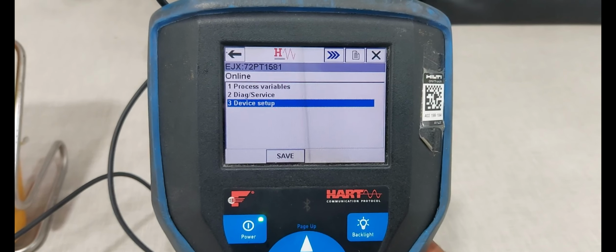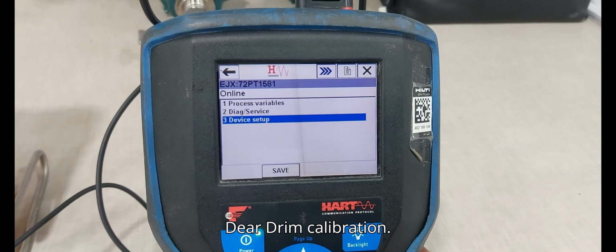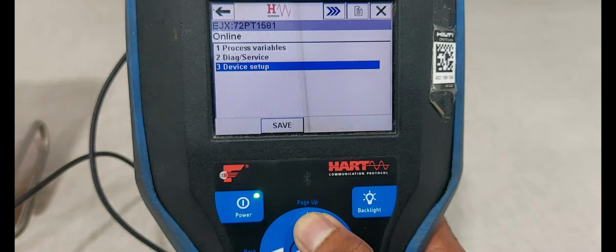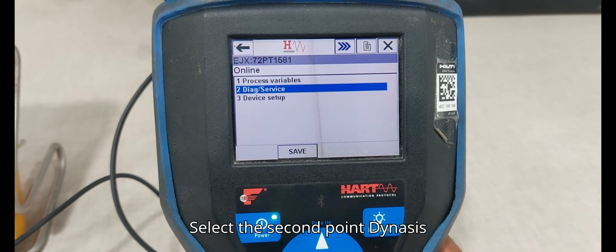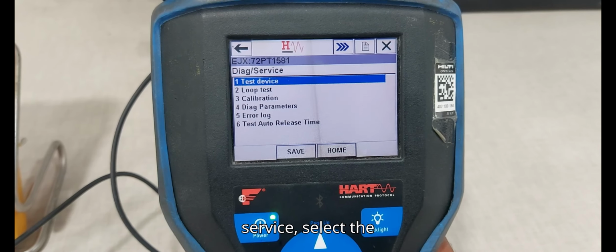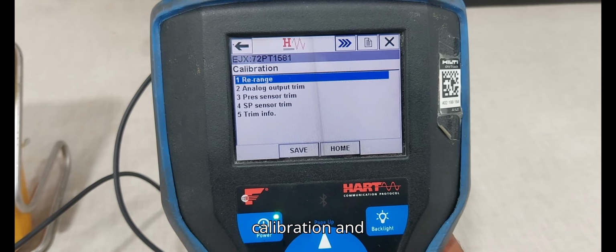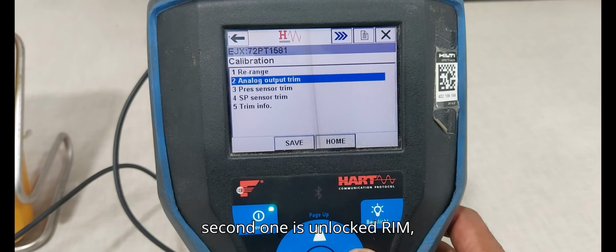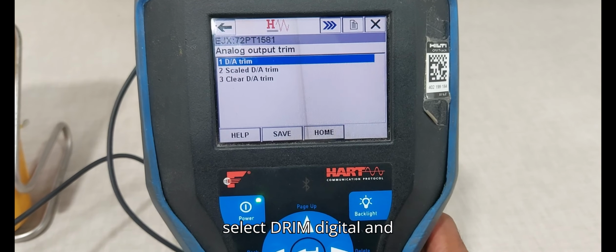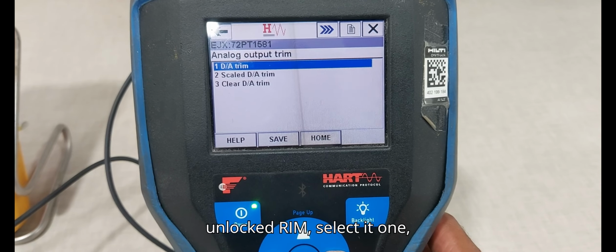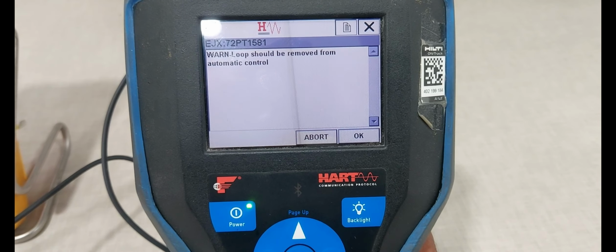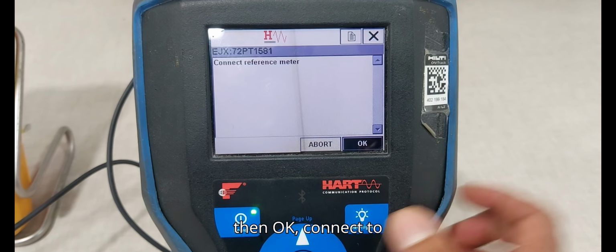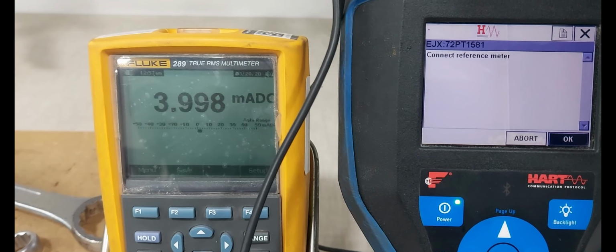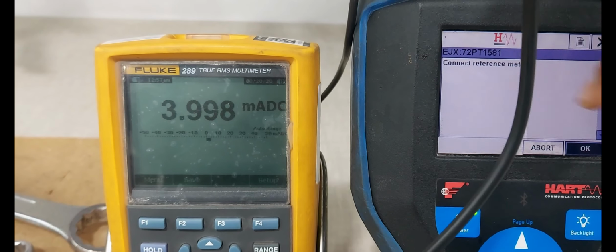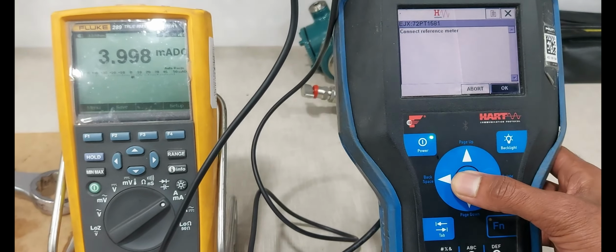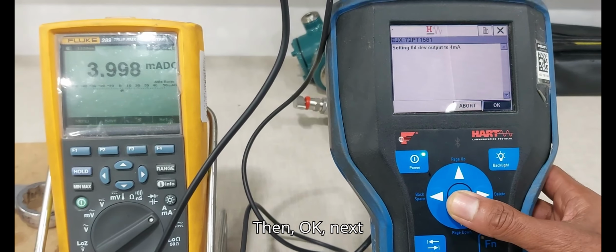Next we are doing DA trim calibration. Select the second point, diagnostic service. Select calibration, and the second one is analog trim. Select D/A trim, digital-to-analog trim. Select it, then OK. Connect the reference meter. The reference multimeter is already connected. Then OK.